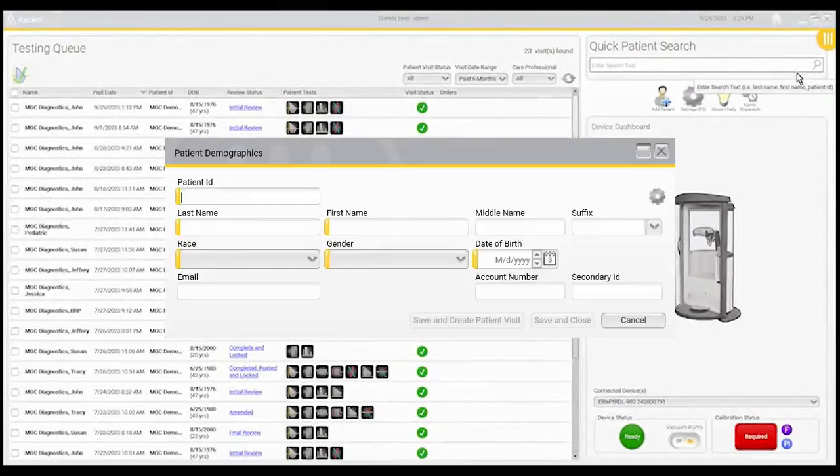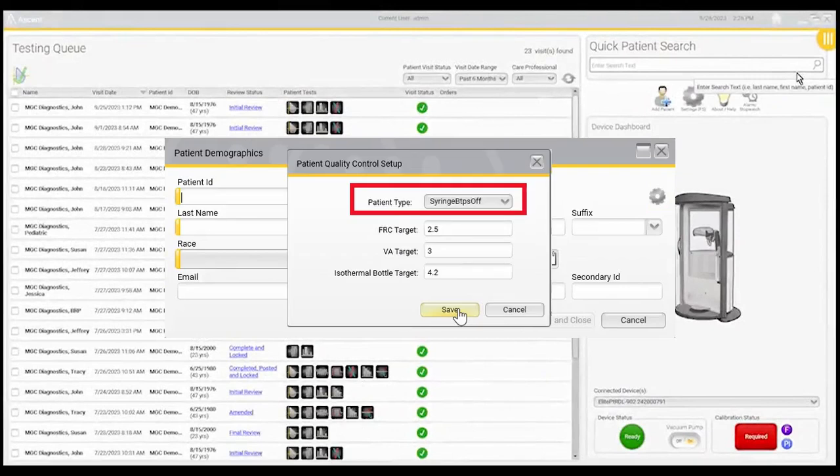For this test, the BTPS correction factor should be turned off. This means that a nitrogen washout syringe QC test can be added to the existing file used for FRC syringe testing.